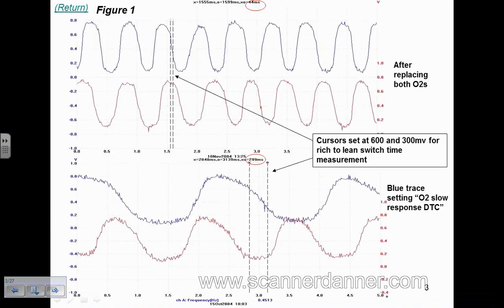If you look at this picture here, we'll talk about this case study in a second. You can see that this blue trace is hitting 800 millivolts, or 0.8, and it's going below 200 millivolts, or 0.2. Looking at the red trace on this side, we're not quite hitting that 0.8 number, but it's good enough.